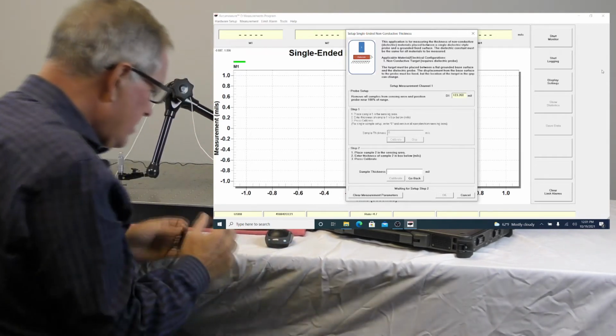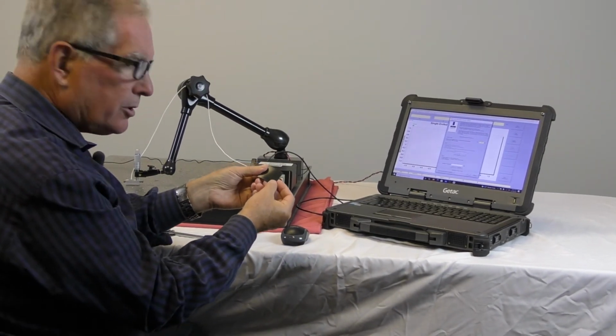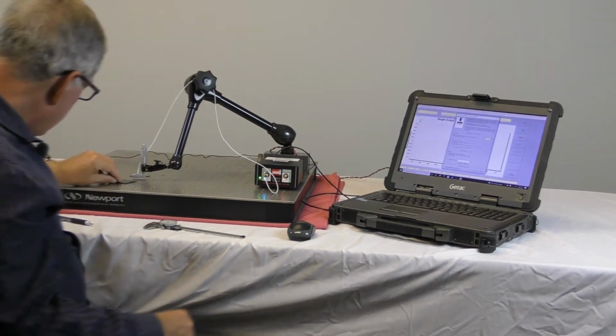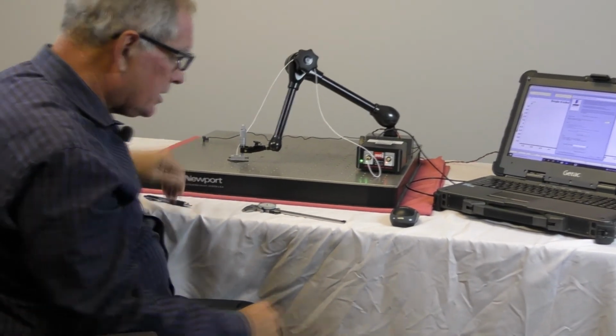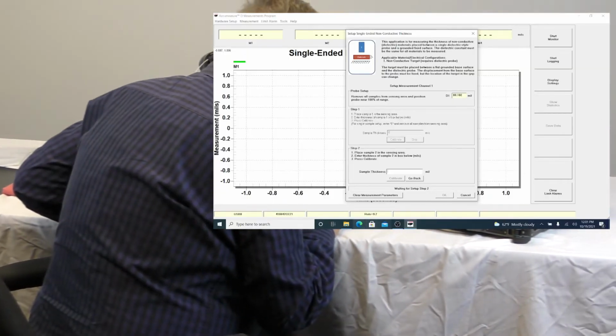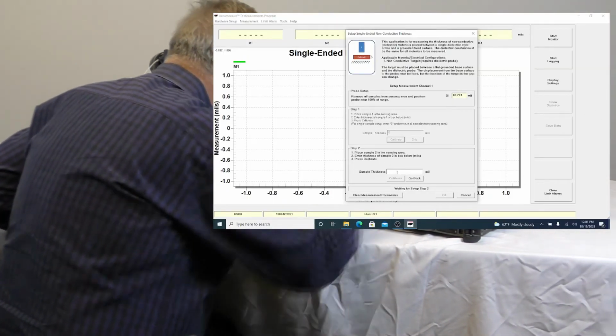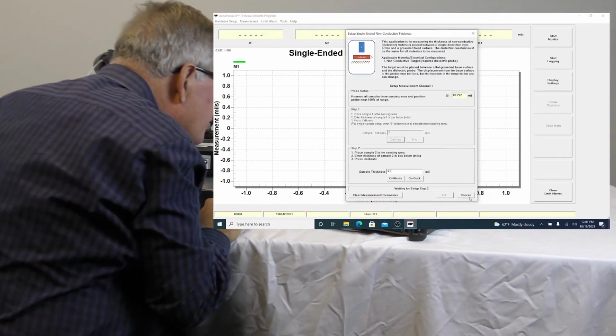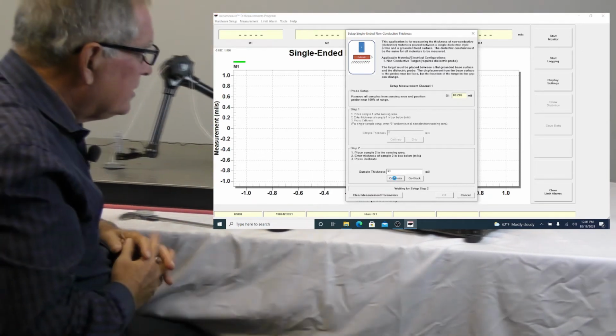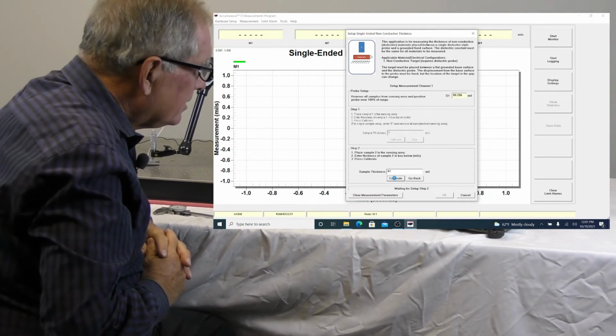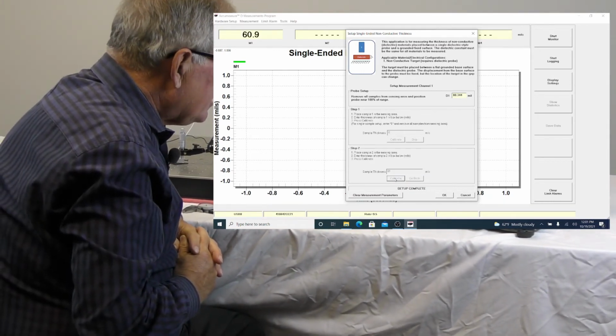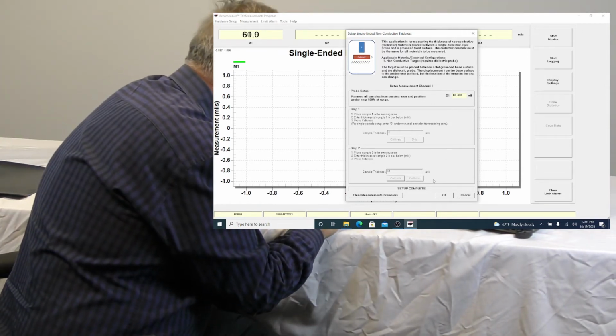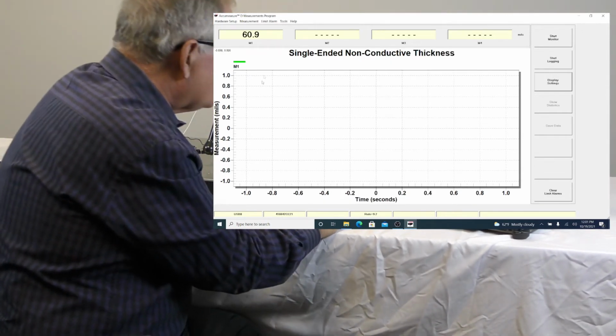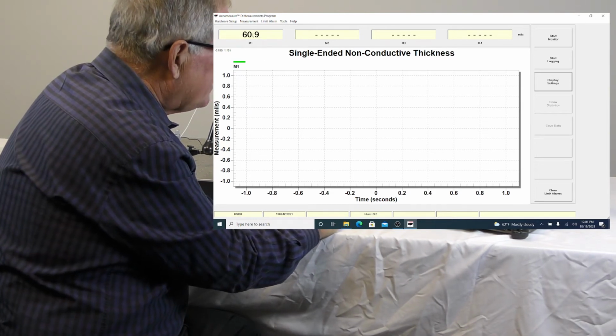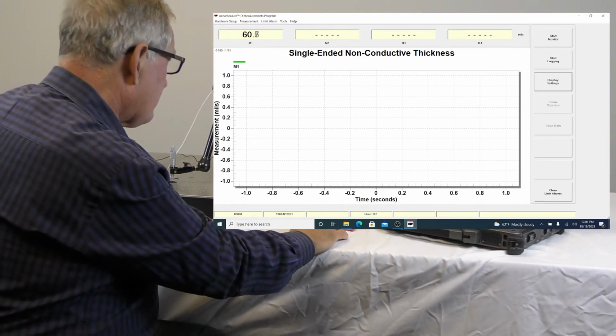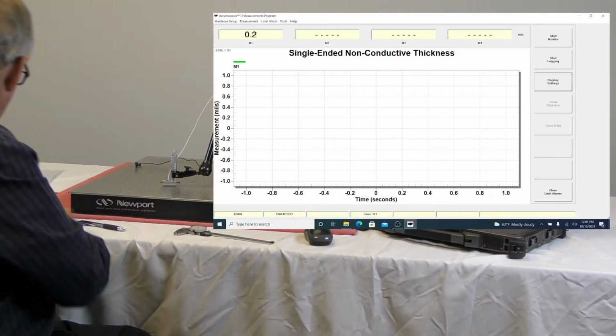Now the next thing we're going to do is, we measured this guy here, and we know he's 61 thousandths of an inch. I'm going to slide this under the probe, our test coupon. Then I'm going to tell the system that this sample is 61 thousandths of an inch, and I hit calibrate. All right, that's it for the calibration. We're all set to go. I hit OK here, and we can see on the test coupon we're reading 60.9. Now, if I slide this out, we'll go back to 0 because there's nothing in the gap.